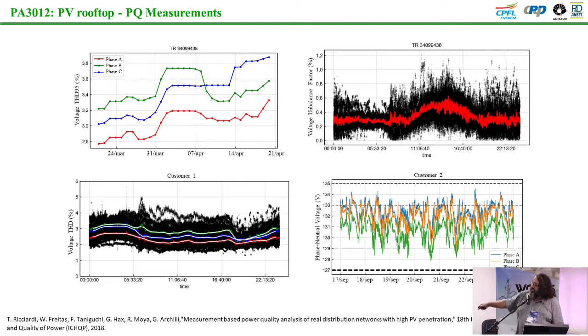For example, here we have the harmonic voltage in a transformer, and you can see the total harmonic distortion, 95th percentile, and these levels are quite okay. This is one of the transformers I showed you, with a lot of PV, and I could not see any problem with voltage harmonics in the transformer.